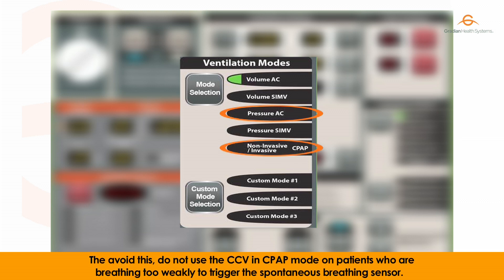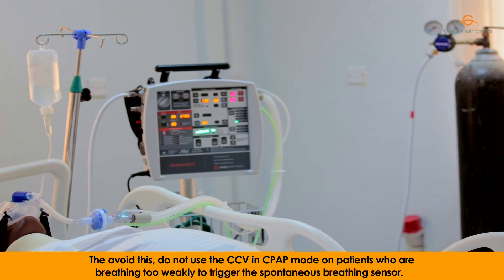To avoid this, do not use the CCV in CPAP mode on patients who are breathing too weakly to trigger the spontaneous breathing sensor.